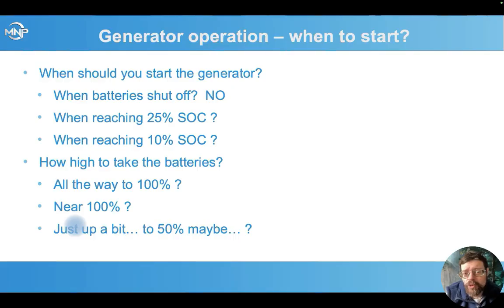I would generally shoot for 20 to 25% as the minimum where I want to start the generator, just to not get too close to that bottom end. The situation where I might go lower is if I know that the sun's coming out in a couple hours. It's early in the morning and batteries are at 25%, but I know that in a couple hours I'll have plenty of sun to recharge them and I won't have to run the generator. Going a little lower might be okay. But if I'm in the middle of 3 weeks of dark fog and I'm at 25%, what does it gain me to go to 10% before starting the generator? It puts off starting the generator for a couple hours, but I know I'm going to have to run it anyway, so I might as well just start it and keep clear of those low state of charge issues with possibly shutting off and having to do a black restart.